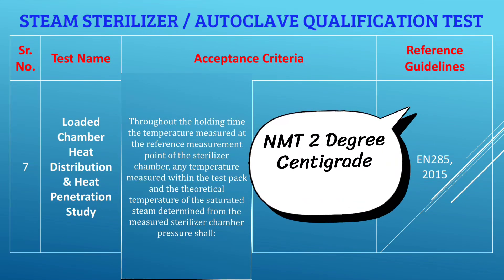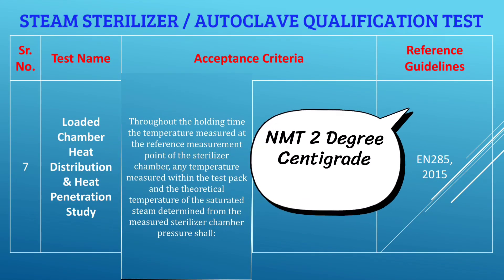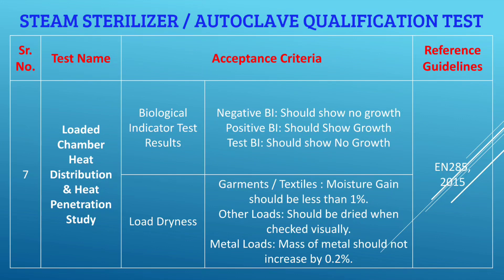Throughout the holding time, the temperature measured at the reference measurement point of the sterilizer chamber, any temperature measured within the test pack, and the theoretical temperature of saturated steam determined from the measured chamber pressure should not differ by more than 2°C. Biological indicator test results: negative BI should show no growth, and positive BI should show growth. For load dryness, moisture gain in garments or textiles should be less than 1%, other loads should be dry when checked visually, and metal load mass should not increase by more than 0.2%, as per EN 285.